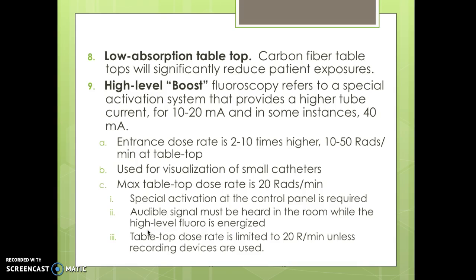High level boost fluoroscopy refers to a special activation system that provides a higher tube current — going from 10 to 20 mA, and in some instances all the way up to 40 mA, compared to the typical 2 to 3 mA. The entrance dose rate is 2 to 10 times higher, approximately 10 to 50 rads per minute at the tabletop. It's used for visualization of small catheters or vessels. The maximum tabletop dose rate for boost is 20 rads per minute, continuous manual activation is required, and an audible signal must be heard from the room when in high level boost.